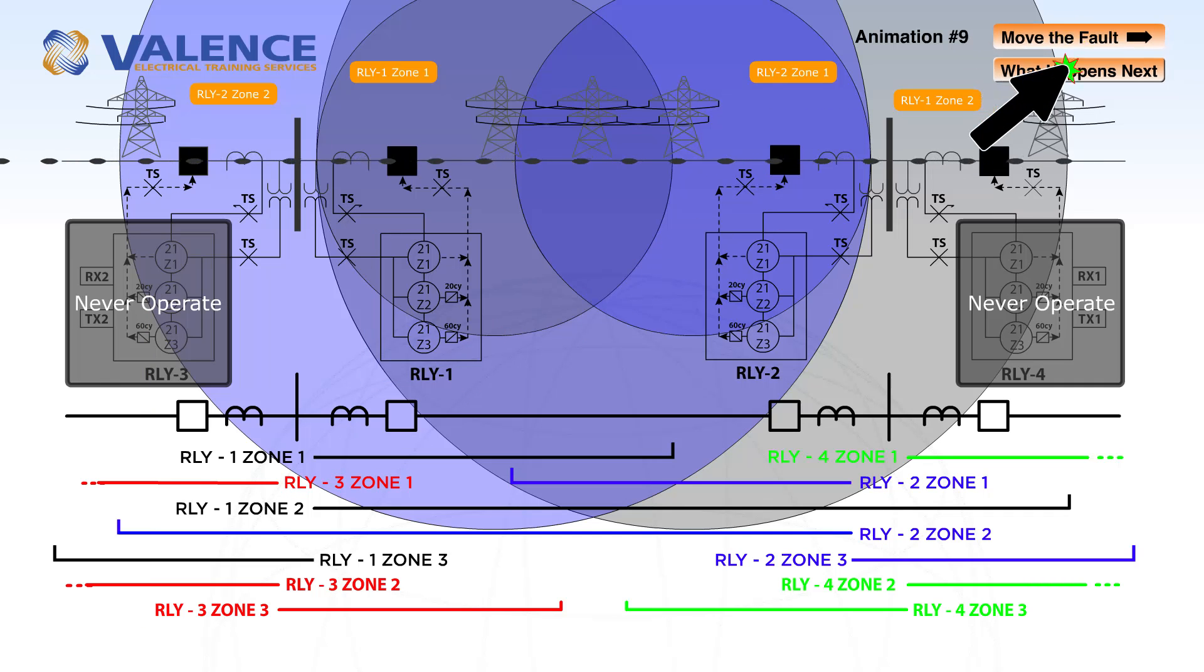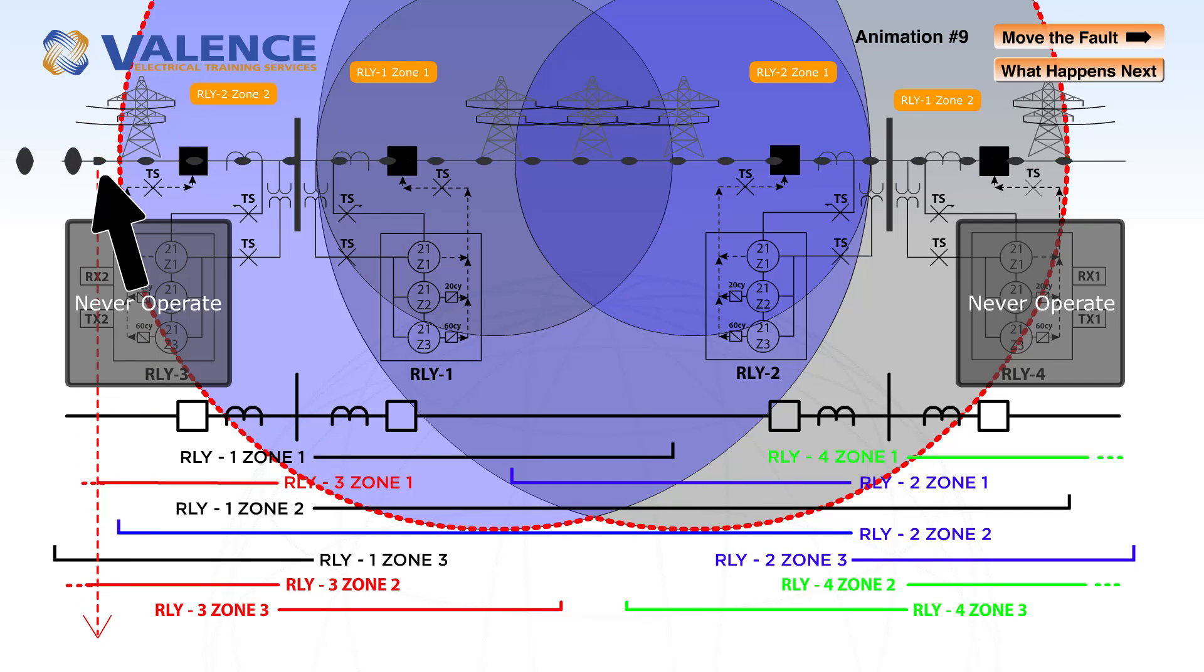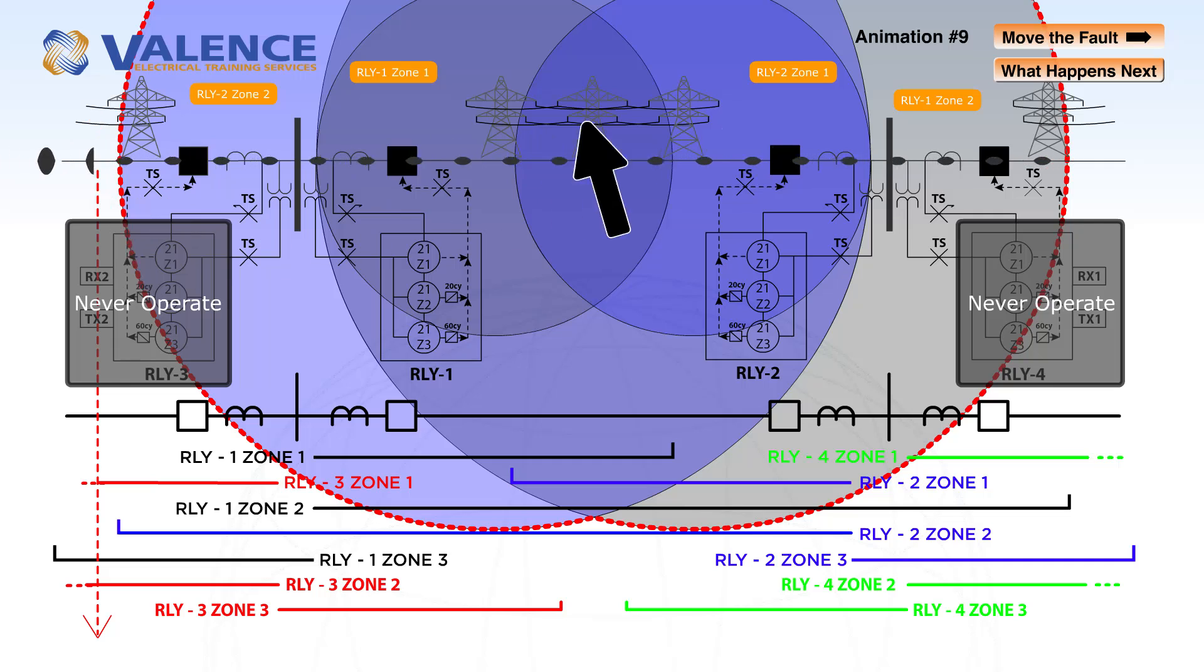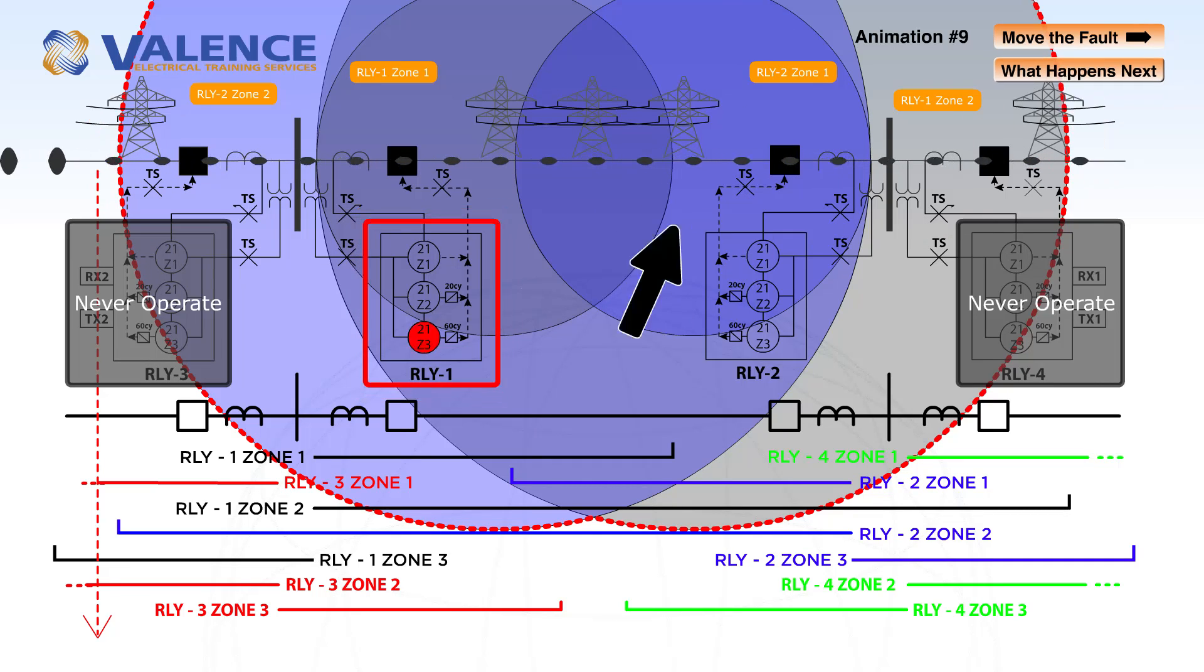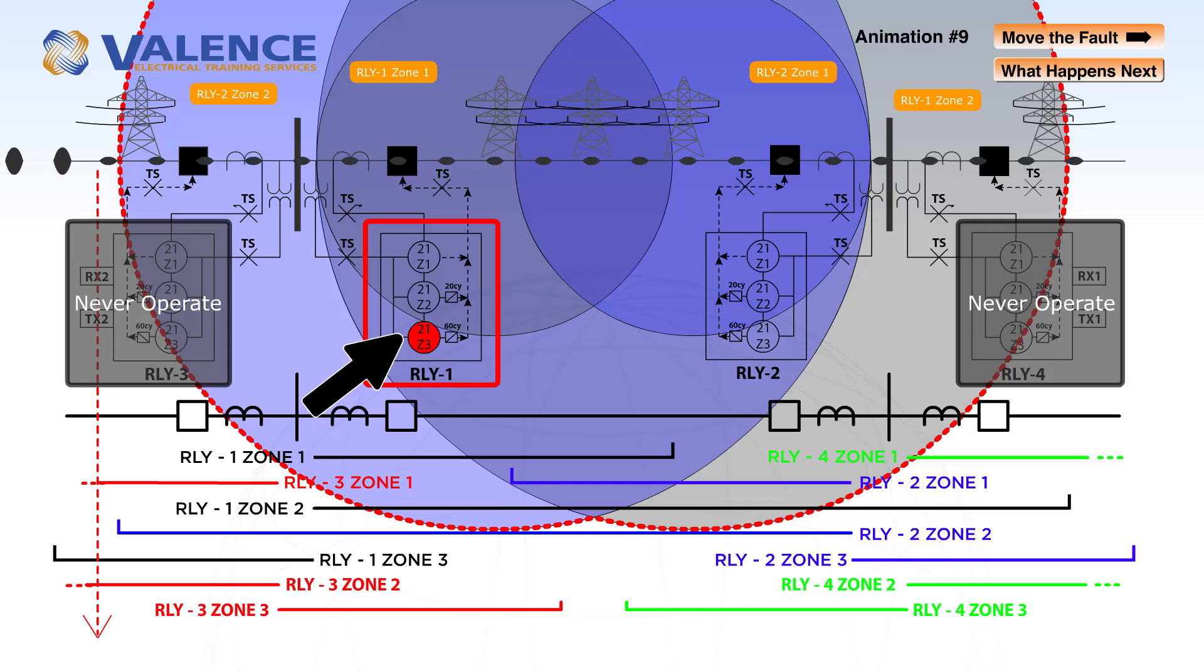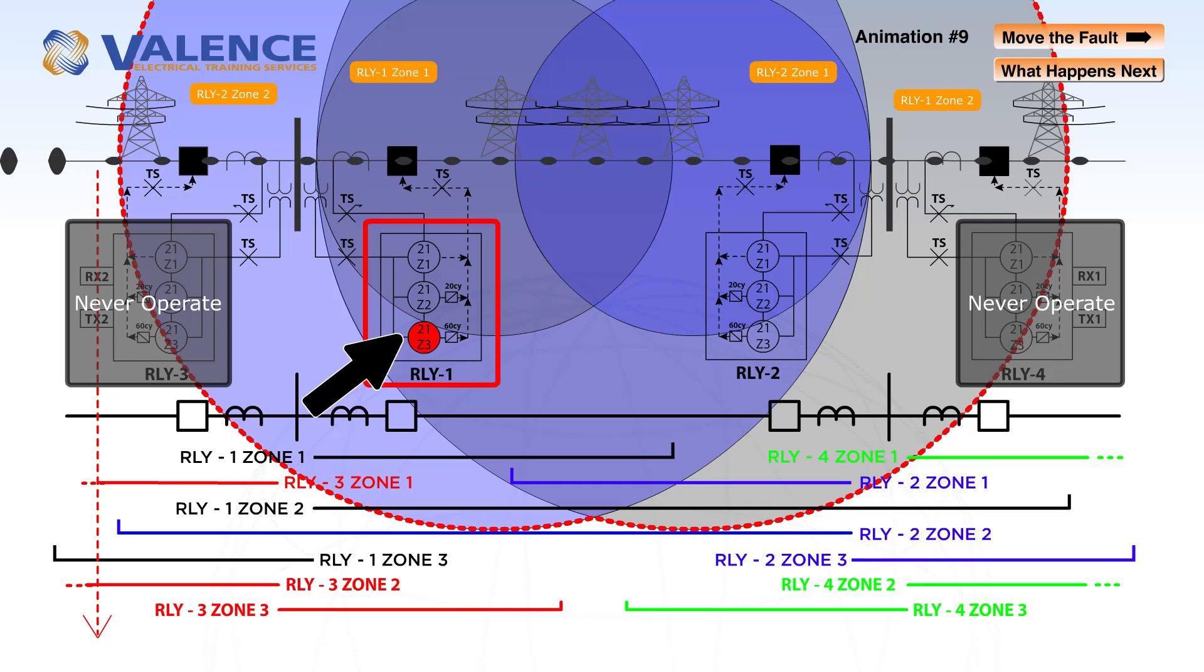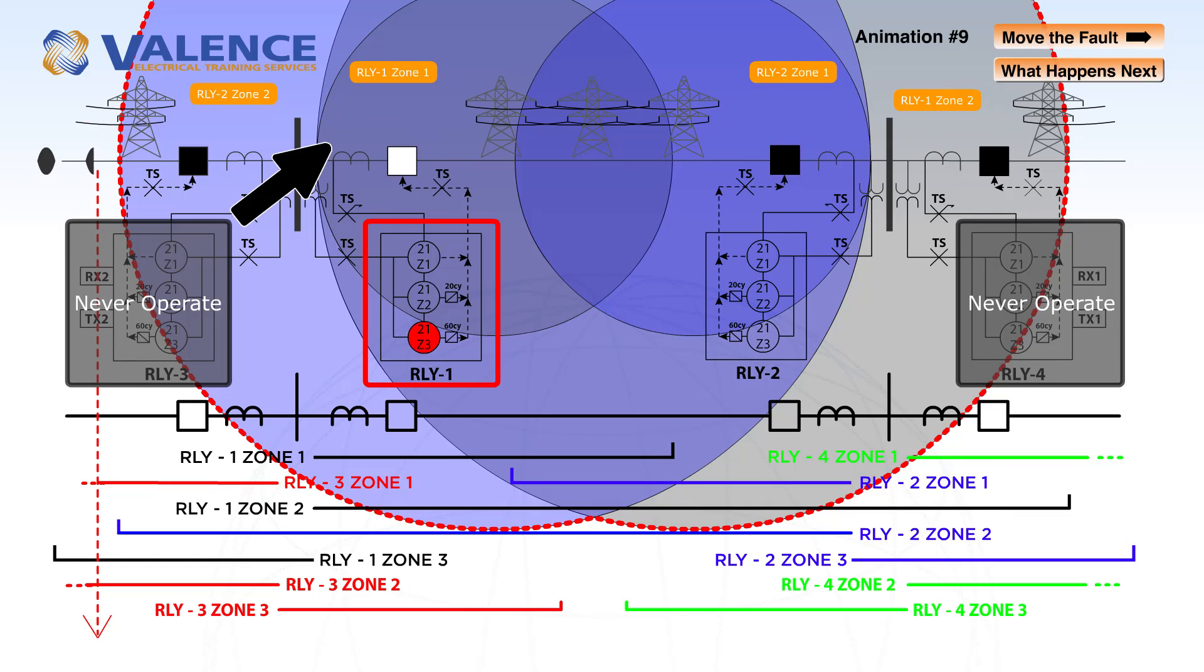If we move the fault outside of relay 2's zone 2 protection, the only element that's going to pick up is relay 1 zone 3. It's operating is the worst case backup scenario, and it will trip after 60 cycles to clear from the rest of the system.